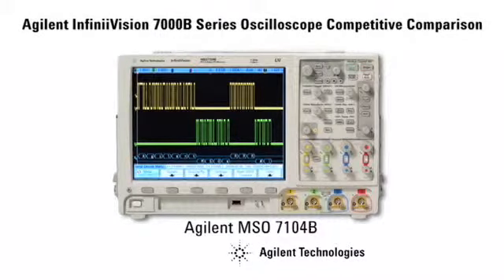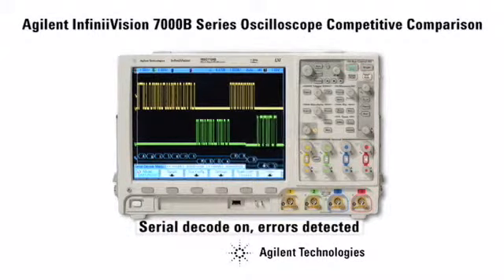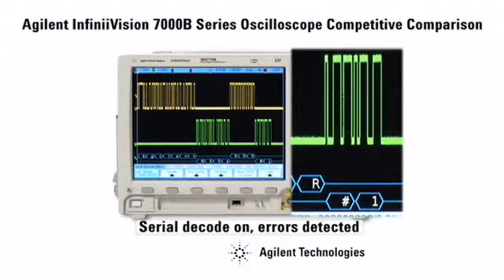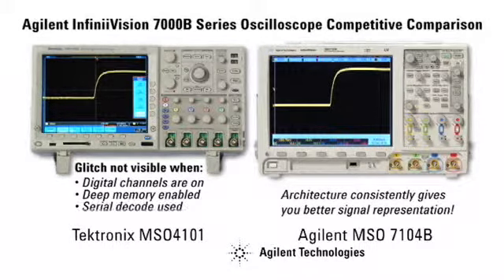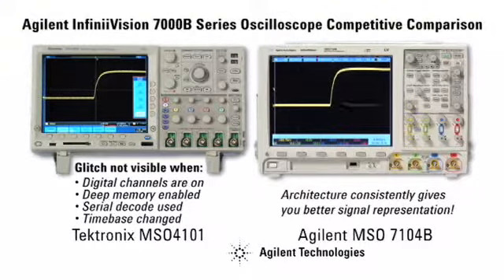Agilent oscilloscopes are the only oscilloscopes in the world that use a hardware-accelerated serial decode, ensuring that you get the best representation of your signal. On the Tektronix scope, when digital channels are turned on, deep memory is enabled, serial decoding is used, or even when the timebase setting is changed, update rates are slowed to the point that analog measurements are compromised and intermittent problems may never be captured.